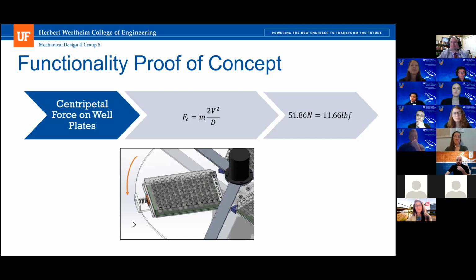For sure, we can shrink some parts in the actual chambers themselves because we made them a little bit longer so that it could allow people to reach in with both hands if needed. But obviously, if we are going to be fitting this in a smaller size, we can for sure take some of the length from the chambers themselves. And also the HVAC component, once we make sure that the wires can reach the power distribution board, we can see if we can shrink that part as well.